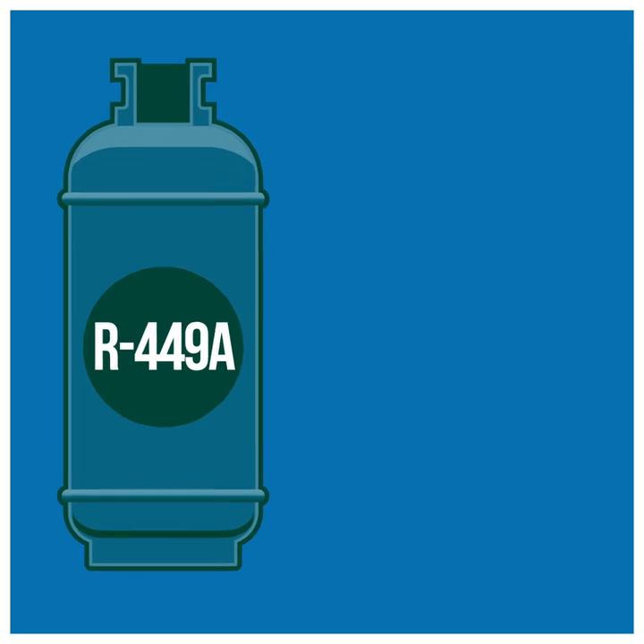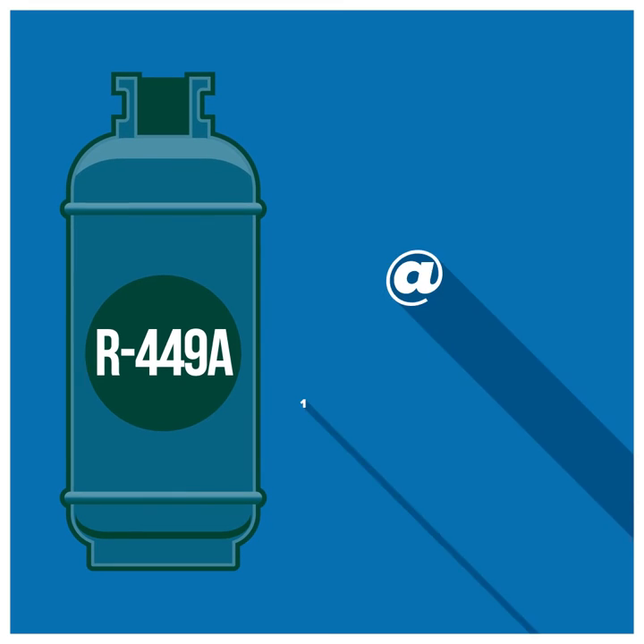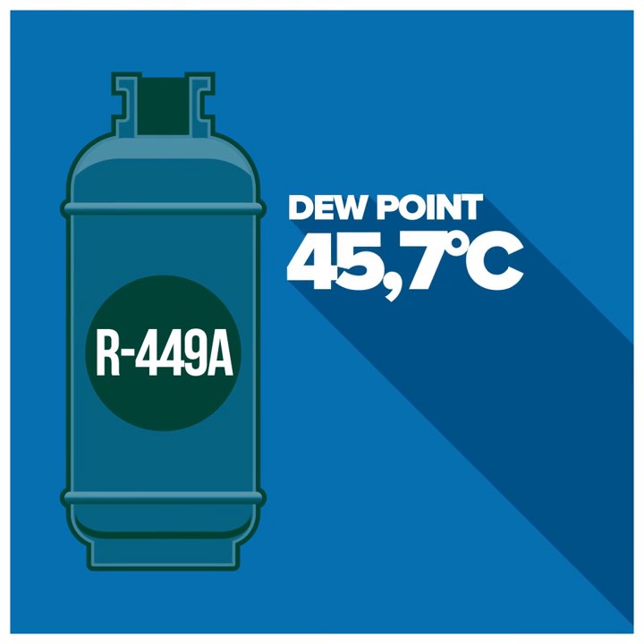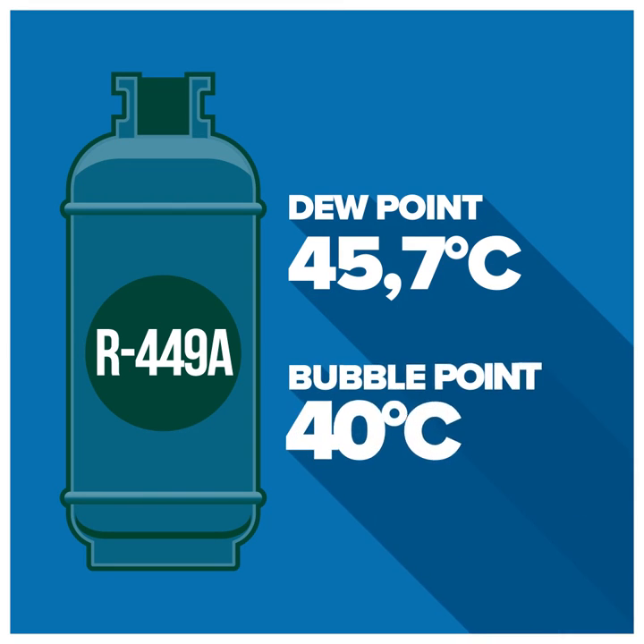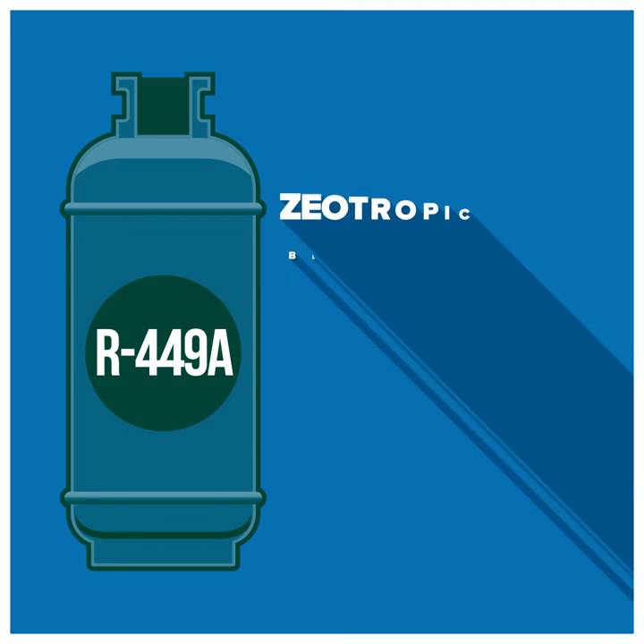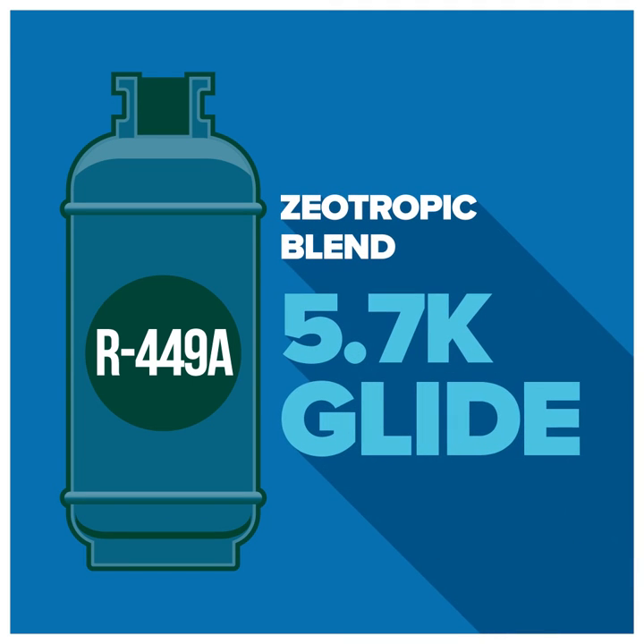For example, R449A at one bar has a dew point — that's the point of condensation — of 45.7 degrees Celsius, and a bubble point — that's the point of evaporation — of 40 degrees Celsius. This means that this particular zeotropic blend would have approximately 5.7K of glide.